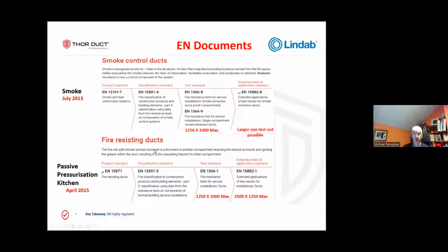And that's a system that's readily available here in Ireland, Thor Duct. One of them is CE marked, one isn't. Simple thing, the product standard for passive pressurization in kitchen wasn't adopted, hasn't been adopted. It's a technical thing. It's really got to do with manufacturing. But you can get a CE marked smoke extract duct on the market right now. By the way, the law states under Regulation 305 that if there's a CE product available, you must use the CE product. That's the rules. So it is available, and CE comes from the factory production control. So just to let you know all those things.